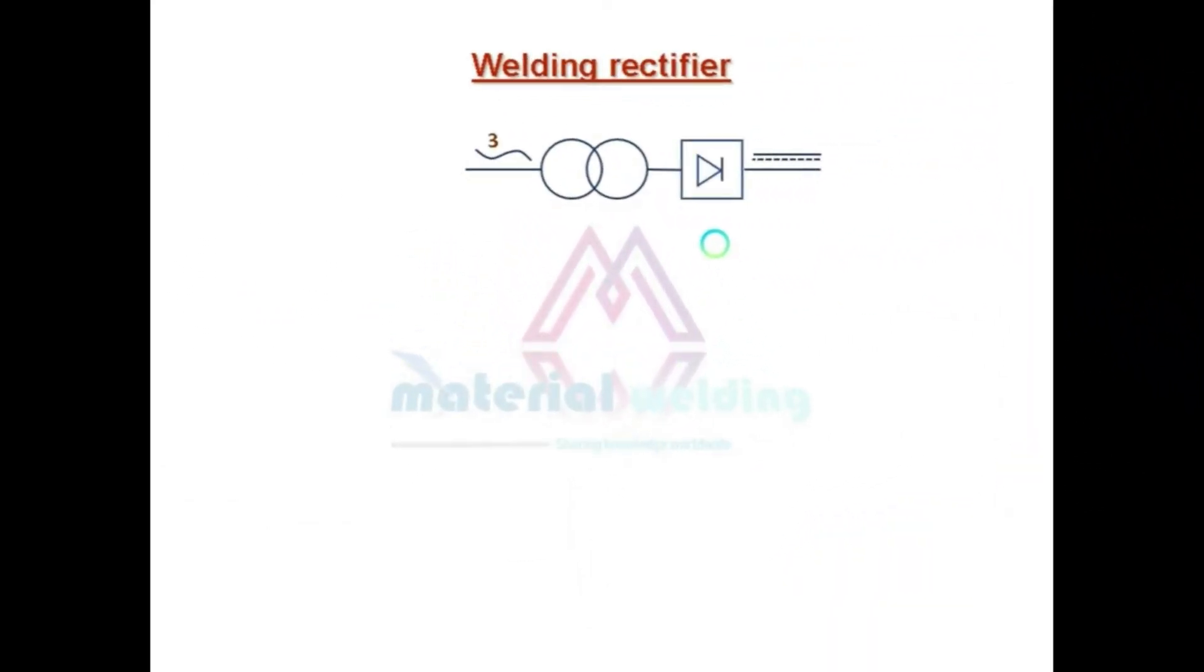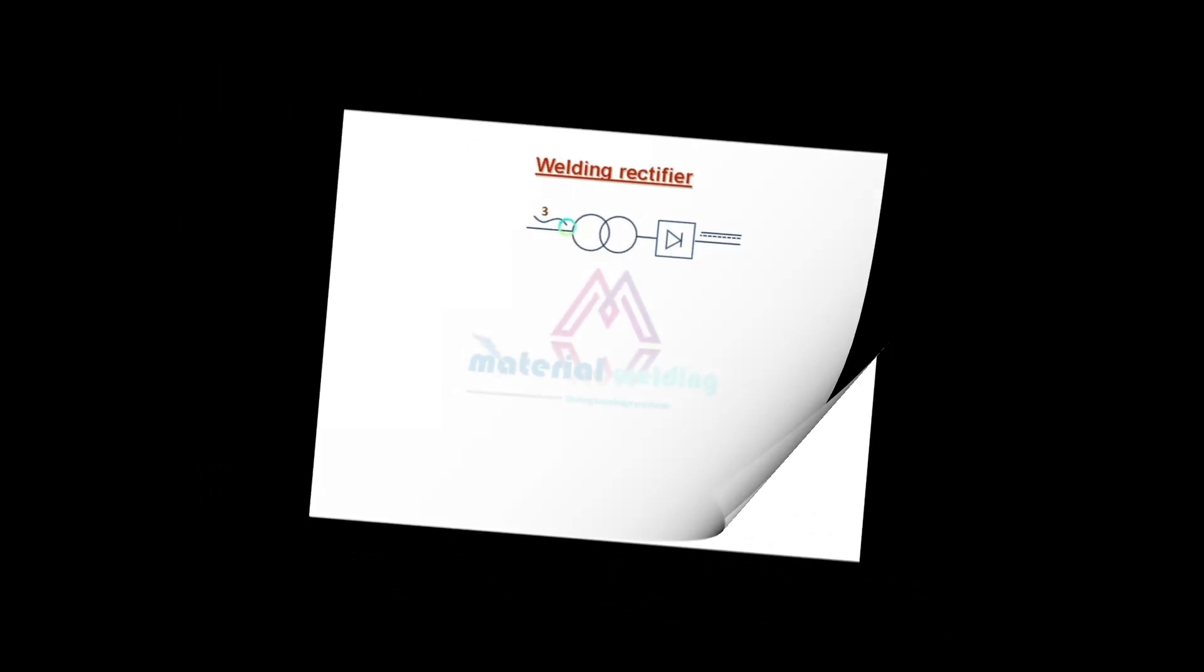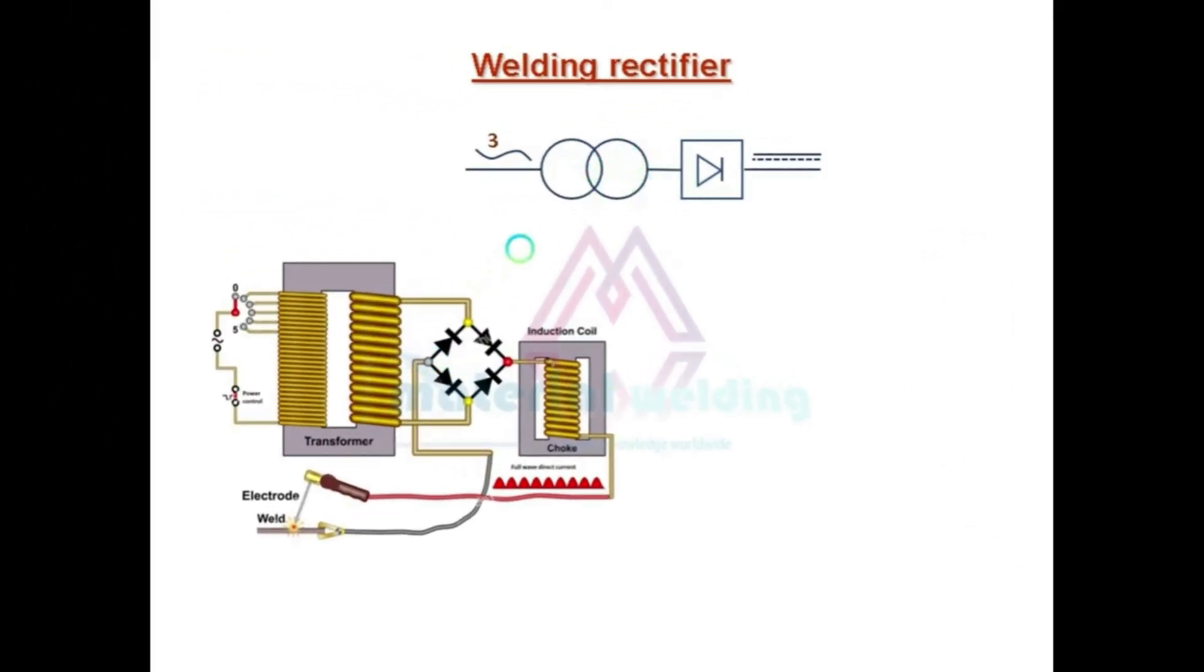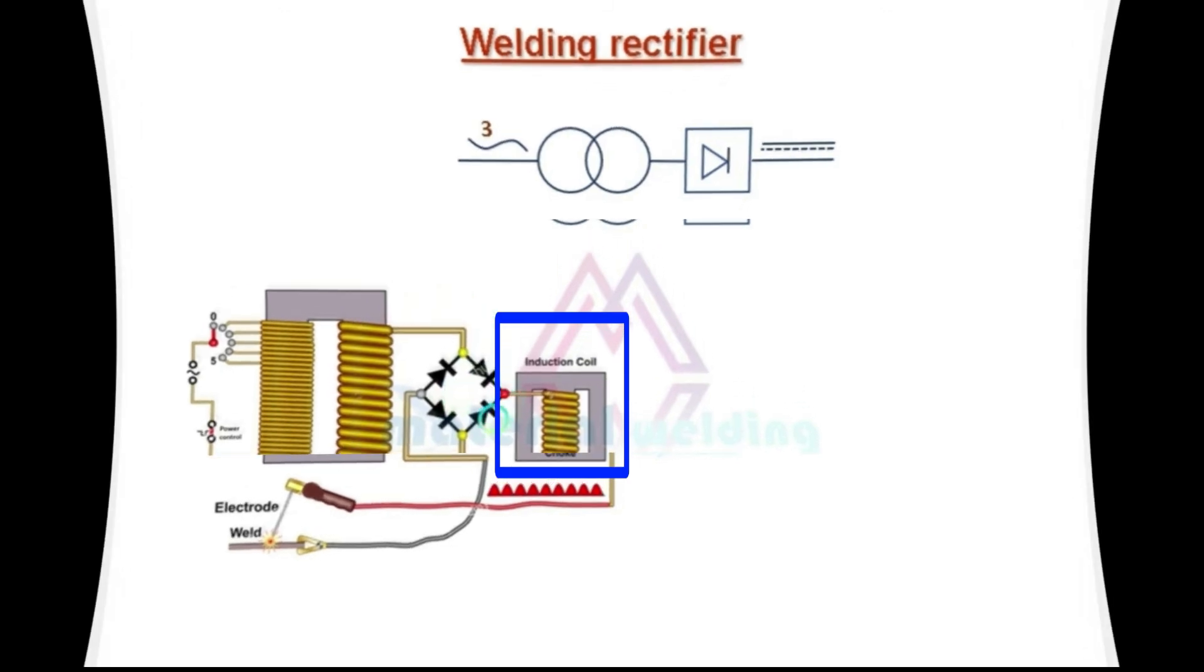Next type is welding rectifier. Here the symbol for the rectifier type welding power sources is shown for viewer learning. As we can see, an input supply of three phase alternating current is first reduced to low voltage and high current using a transformer and then rectified to direct current using a bridge rectifier. So bridge rectifier is basically an arrangement of diodes. A choking device is used to smooth the output direct current for smoother welding operations.